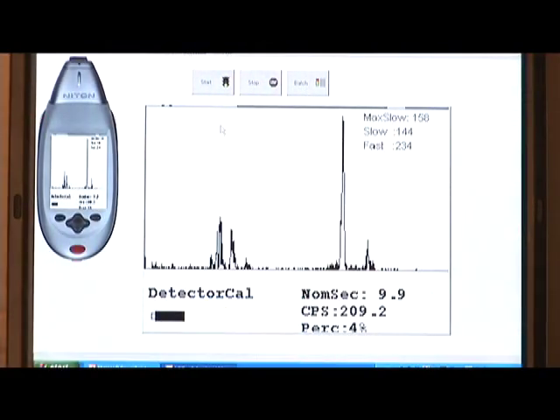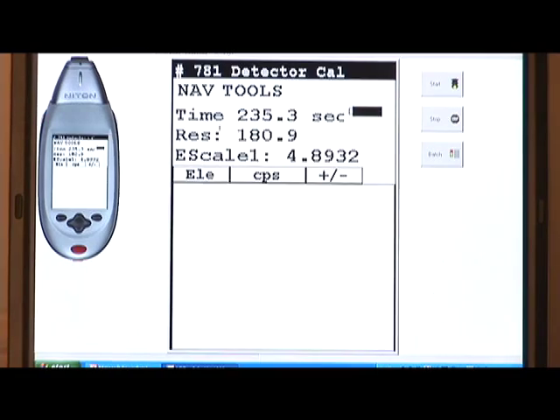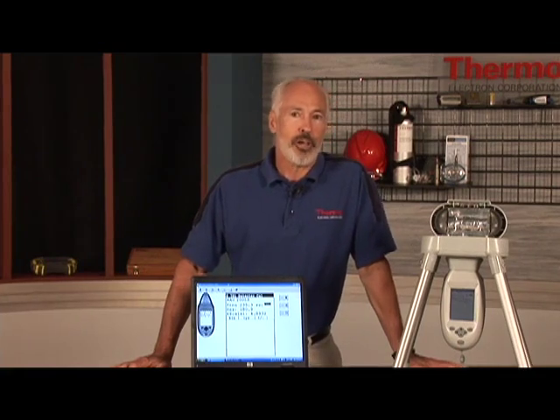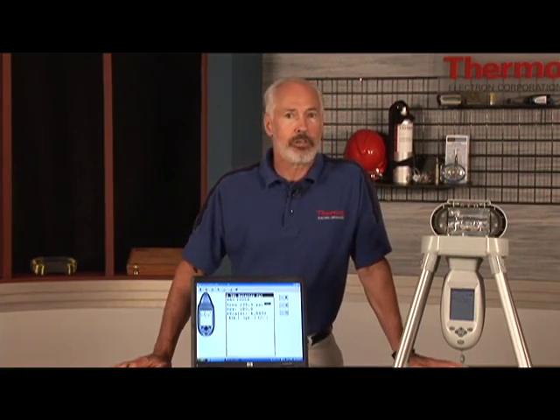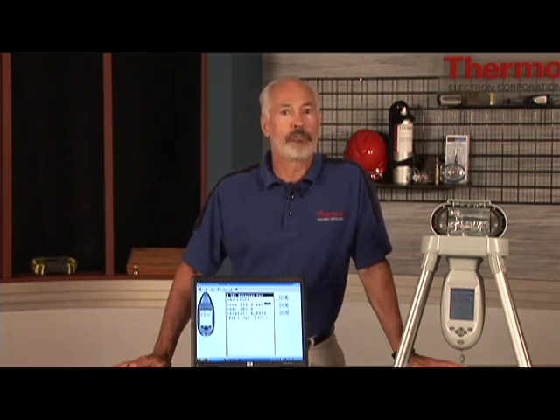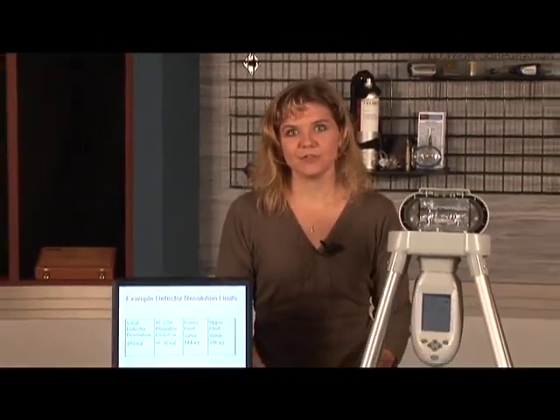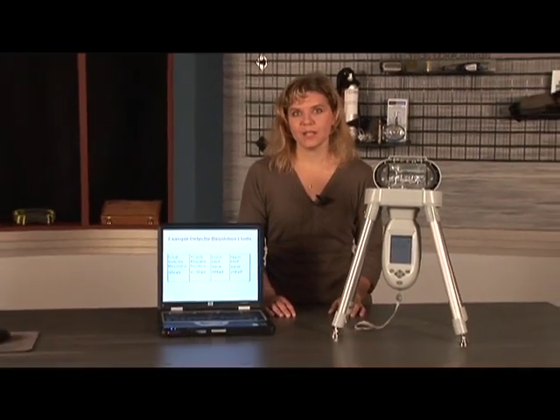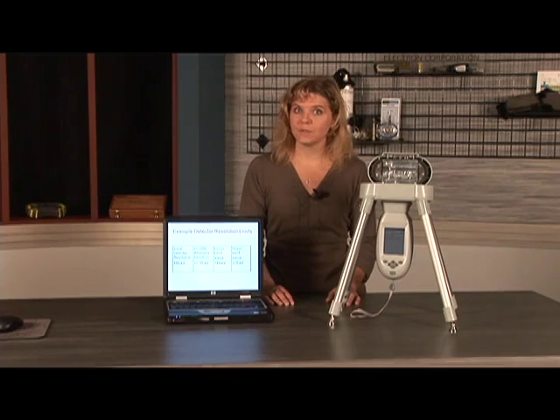At the conclusion of the detector calibration, the analyzer will display the results as shown here. A good diagnostic indicator of detector stability is the degree of change of the detector resolution value. We recommend monitoring this value at the conclusion of each detector calibration. If this value goes beyond the plus or minus 20% range, contact your nearest service center for assistance. For this reason, you will want to record the values of resolution from the detector calibration that you just performed. This will give you the initial value for future comparison.